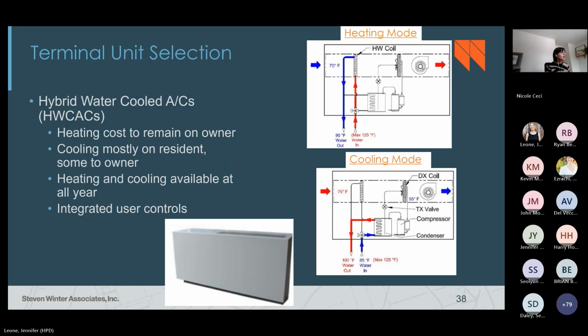I mentioned I'd dive in a bit more on terminal units and where that simultaneous heating and cooling ability comes from. There are many different terminal units that could be used with this system — it's an open source system. I tend to like hybrid water-cooled ACs because they use a low temperature fan coil for heating and a water source heat pump section for cooling, giving you simultaneous year-round heating and cooling ability.